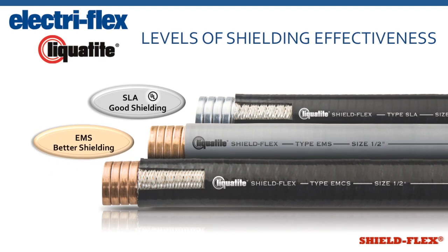Type EMS, the next one down, offers a better shielding effectiveness than Type SLA. It has an inner core made from a fully interlocked bronze strip and does not contain a braided shield. Then an all-temperature PVC jacket is extruded over the core, resulting in a sealed, waterproof raceway when assembled with liquid-tight fittings. Finally, the Type EMCS offers the best shielding performance of these 3 and is a hybrid of both SLA and EMS because it utilizes the same bronze core and PVC jacket as EMS, but gets further screening protection from a tinned copper braid as found in the SLA product.